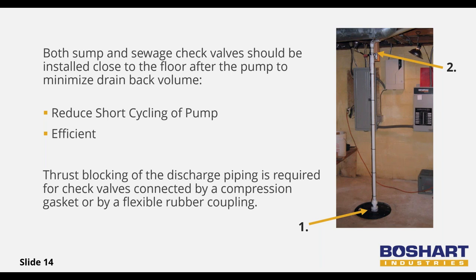When installing valves with flexible rubber couplings or compression gasket connections, thrust blocking is required to prevent lateral movement or blow-off that could separate those connections. You can see the wooden thrust protection installed at the top of the piping in arrow two. Not all plumbing codes are equal, so it is the responsibility of the installer to understand the local code before installing a system.